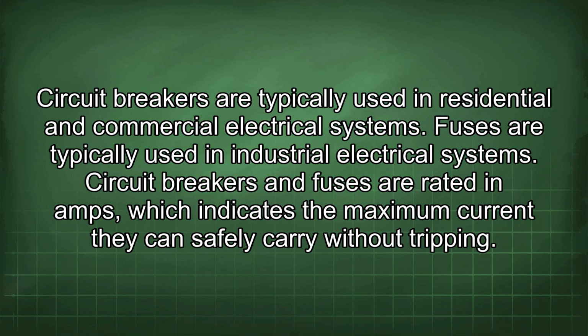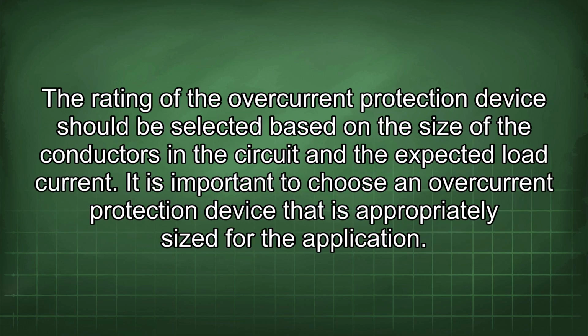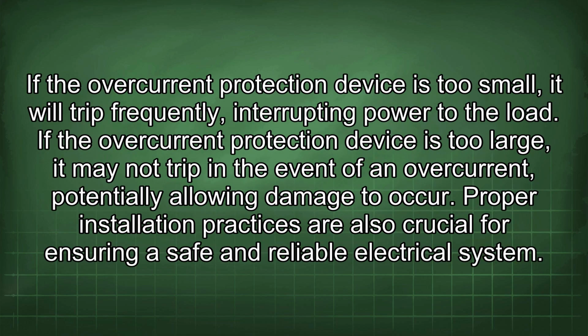Circuit breakers and fuses are rated in amps, which indicates the maximum current they can safely carry without tripping. The rating of the overcurrent protection device should be selected based on the size of the conductors in the circuit and the expected load current. It is important to choose an overcurrent protection device that is appropriately sized for the application. If the overcurrent protection device is too small, it will trip frequently, interrupting power to the load. If it is too large, it may not trip in the event of an overcurrent, potentially allowing damage to occur.